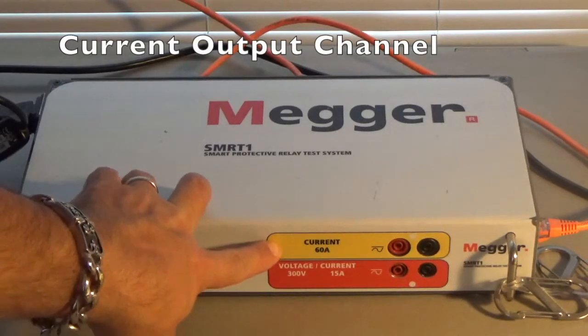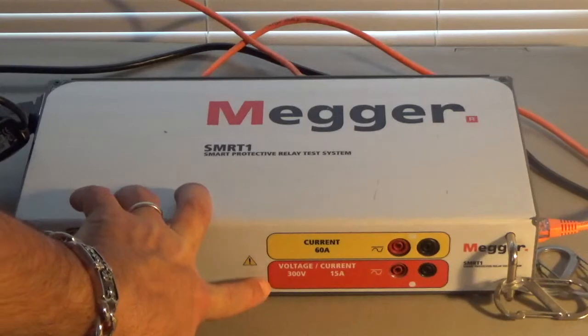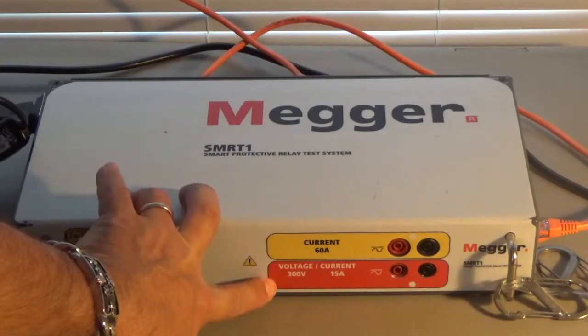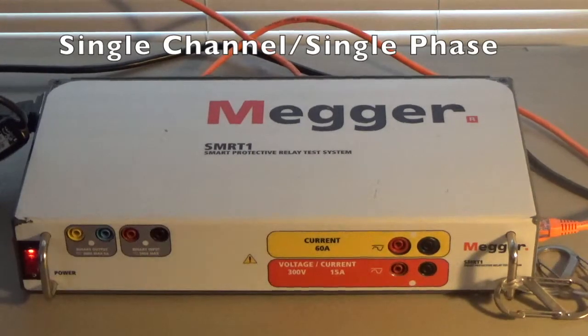At the top here you have the current output which maxes out at 60 amps. You have the voltage output here that maxes out at 300 volts at 15 amps. You can also convert this voltage channel into a current channel if you so wish. It's a single channel or single phase relay test set.